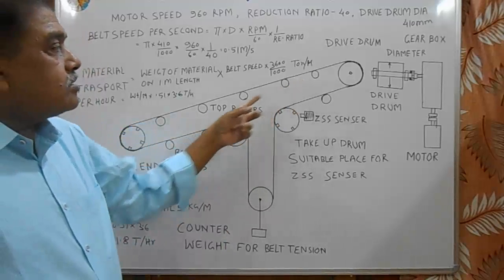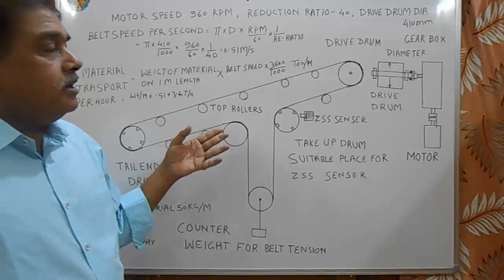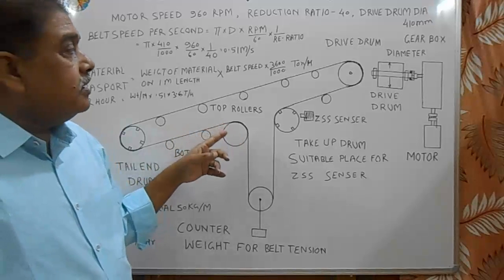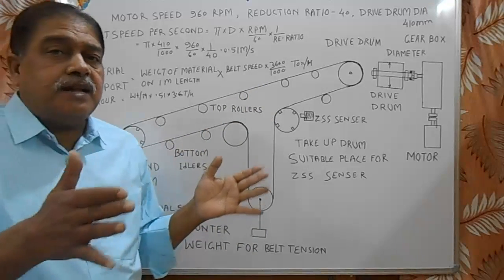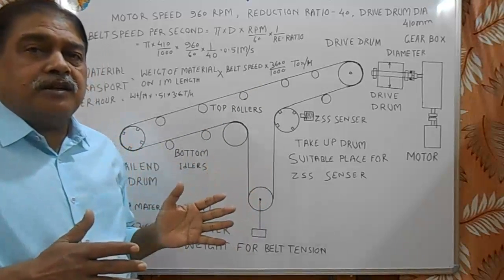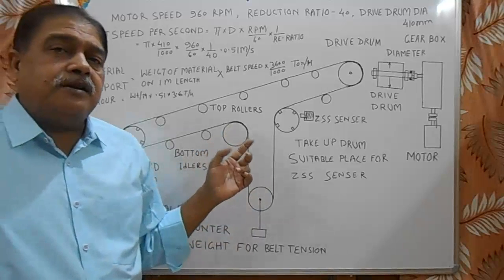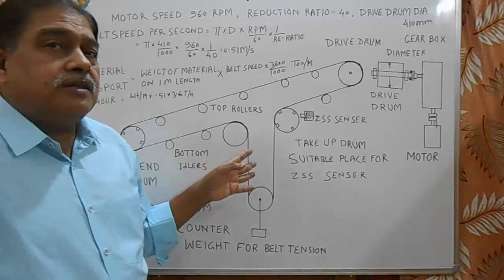Here a number of pull cord switches are provided so that operator can stop the belt from any pull cord switch. In addition to that, belt sway switches are provided on both sides of the belt conveyor. So if belt sways to any side of the center, then the belt switch operates and belt stops. This way stops the spillage of material.